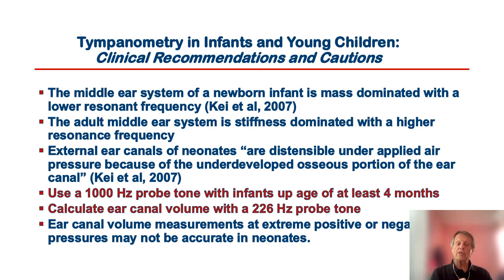The low-frequency probe tone in an infant is used to calculate ear canal volume. The high-frequency probe tone actually measures the function of the middle ear. And I think most of you are familiar with this, but it's always important to emphasize: when you purchase a piece of equipment, if you're going to be seeing infants, you must have the high-frequency probe tone option.